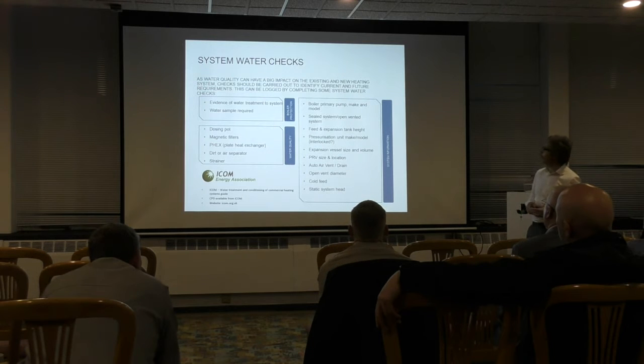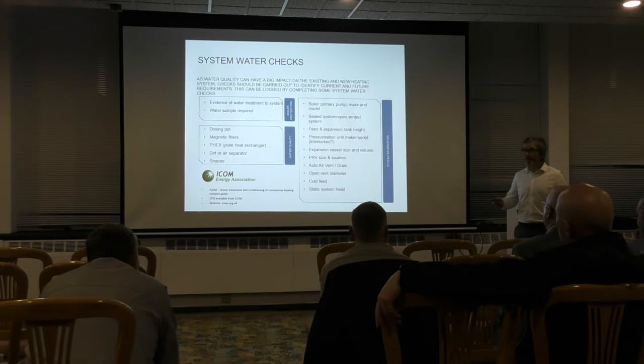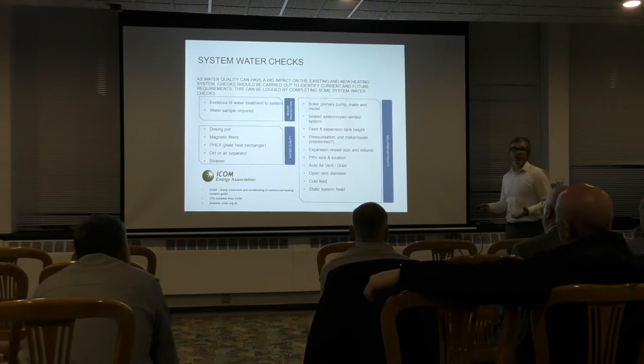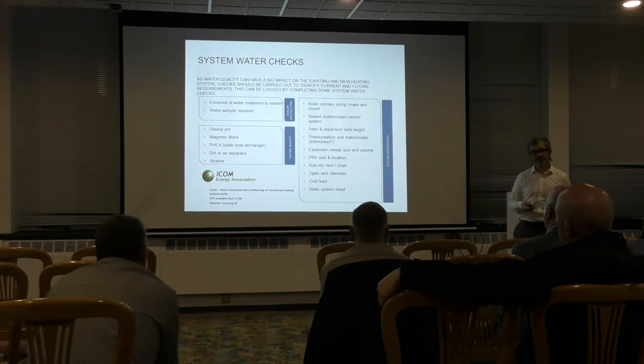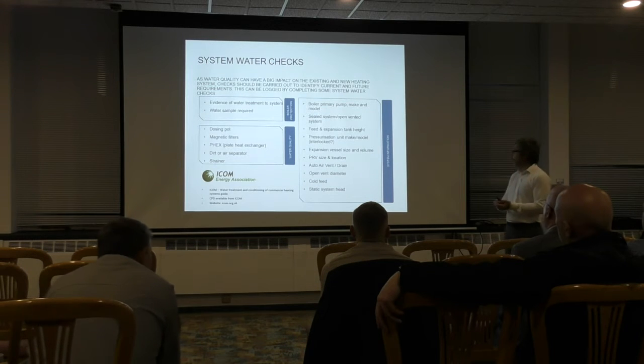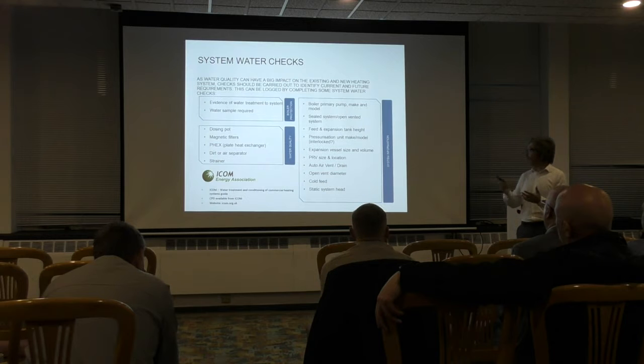Obviously, the system itself, is it a sealed system or open vented system? Obviously, open vented is pretty old school. We don't really see open vented systems that much. In older buildings, yeah, we do. Normally, common or good practice will be to change that over to a sealed system. You could keep it as an open vented system, and there's boilers out there that are okay. Modern condensing boilers are okay on open vented systems, but there are modern condensing boilers out there that aren't. But every single modern condensing boiler out there is going to be okay on a sealed system. So again, if you don't change that, you're just narrowing down your boiler selection as well.